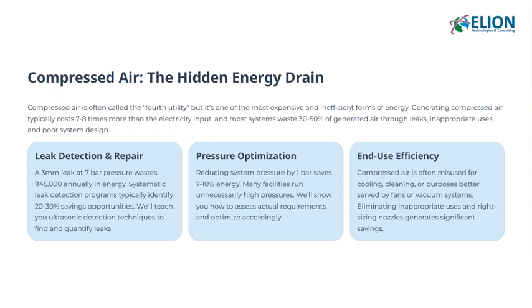Next, let's discuss pressure optimization. Reducing your system pressure by just 1 bar can save between 7 to 10% of energy. Many facilities run their systems at higher pressures than necessary, which leads to unnecessary energy consumption. We'll show you how to assess your actual requirements and adjust accordingly to save energy without sacrificing performance.